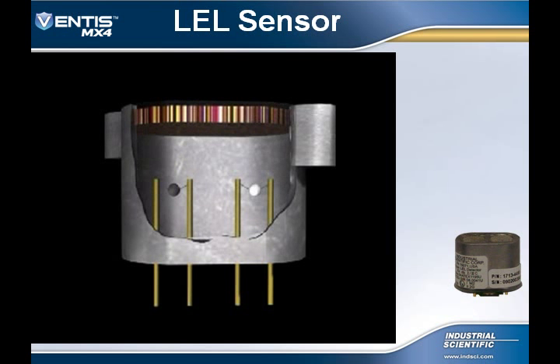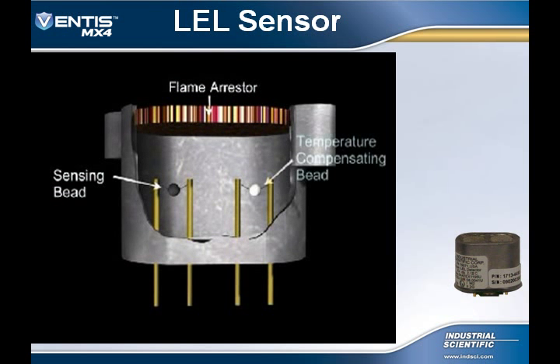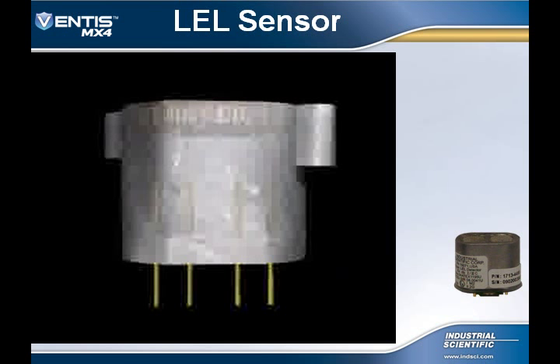Inside this catalytic diffusion sensor are 2 beads. One is called the sensing bead, which is the one that burns the combustible gas, and the other bead is called the temperature compensating bead, which doesn't see any of the combustible gas at all. Both of these beads in fresh air will operate at a temperature of approximately 500 degrees Celsius.